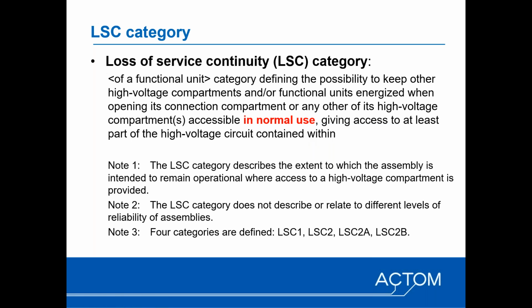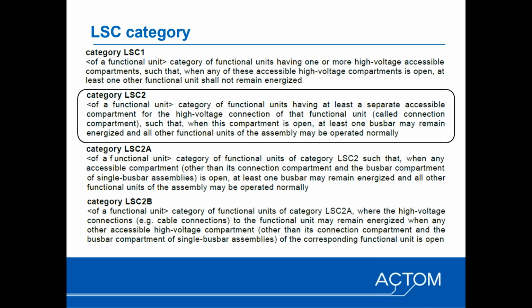Something else that's covered, again, I won't go into the details of the different definitions, is loss of service continuity, an important classification that was introduced into the 62271 series of standards. It's effectively a category defining the possibility to keep other high voltage compartments of a functional unit energized, as well as adjacent functional units, when opening its connection compartment, which is the cable compartment, or any other of its high voltage compartments in normal use. So it only applies to compartments that require access in normal use. There are four definitions, and these will be in the notes, but I just want to home in on LSC 2.